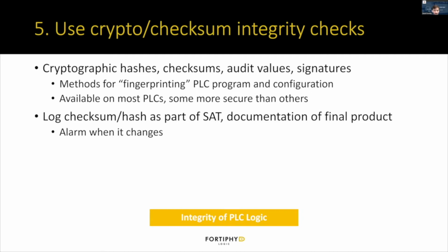CODESYS has a lot of different options here. And so what you want to do is log this as part of maybe the site acceptance testing, when the program is actually deployed on site, saying this is the final production fingerprint of the PLC program, and this is the gold version. And in the future, you want to alarm when that changes and just document each major version, so you have that hash or that checksum to identify what that version was.